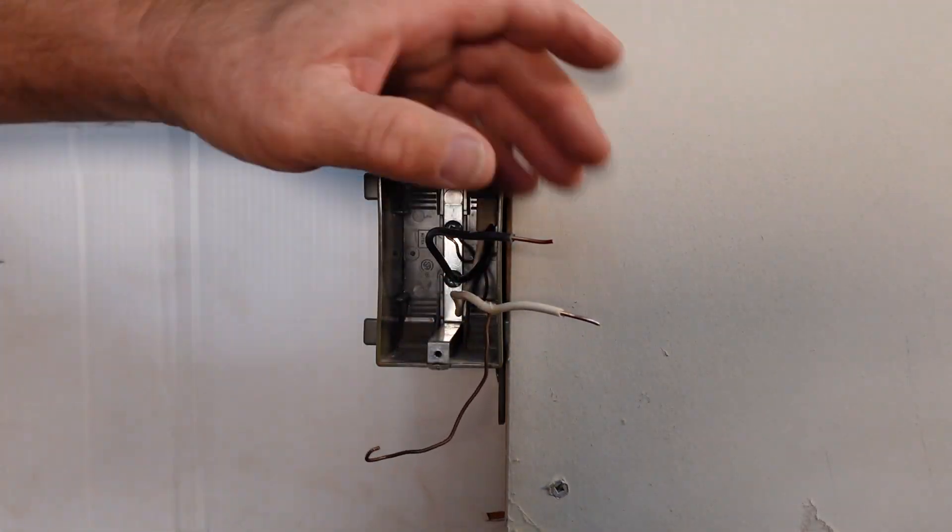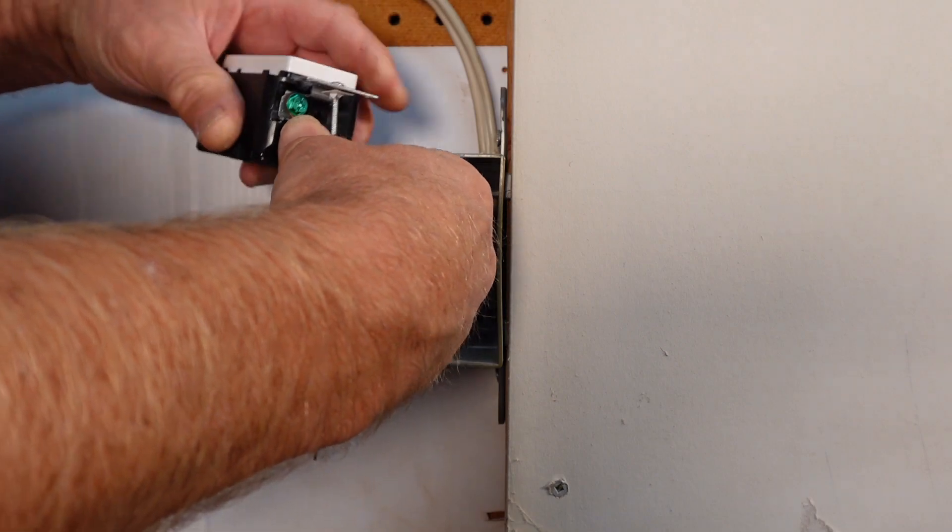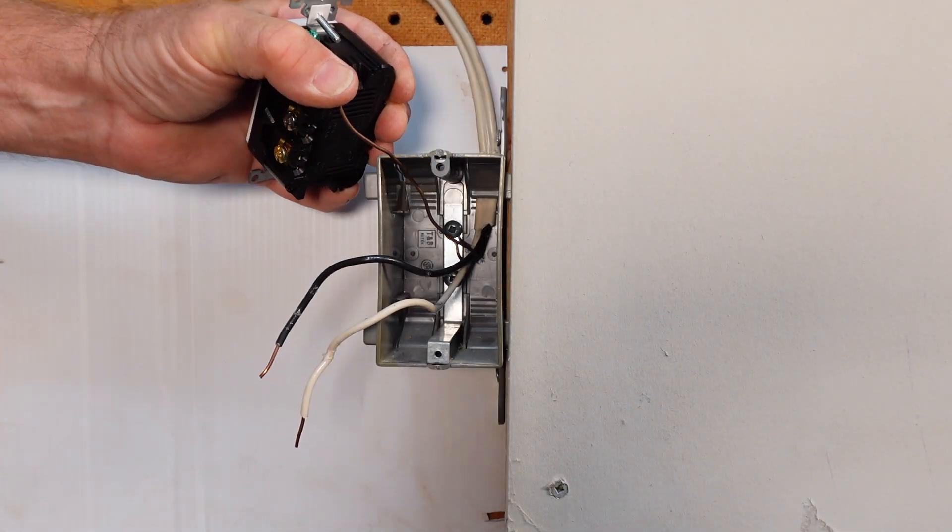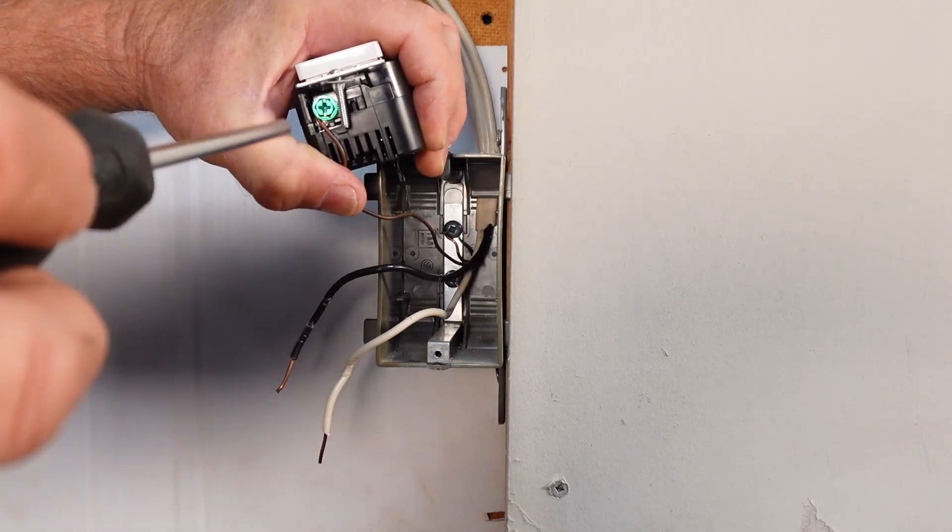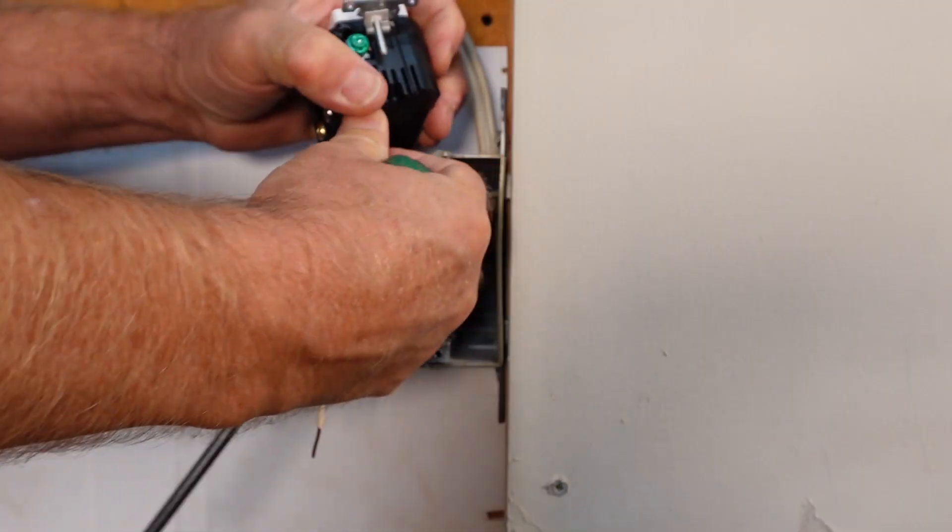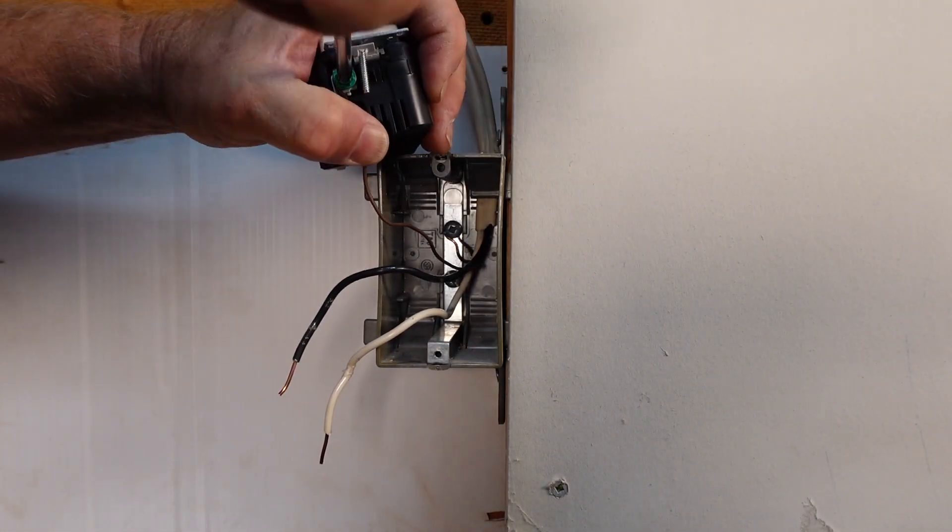So first things first I always connect the ground wire first and if you haven't watched other my other videos when I'm doing any wiring I like to work, when disconnecting a device I always like to go from disconnect the hot first, the neutral second, the ground last and when reconnecting a device I always like to connect ground first.